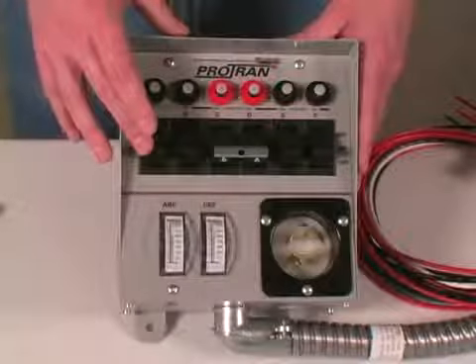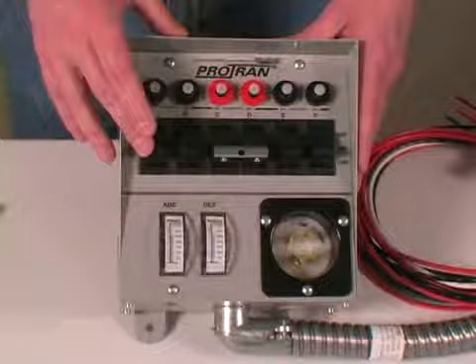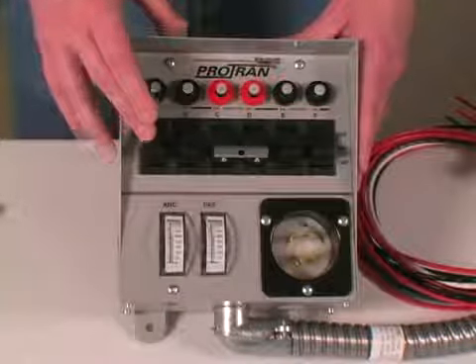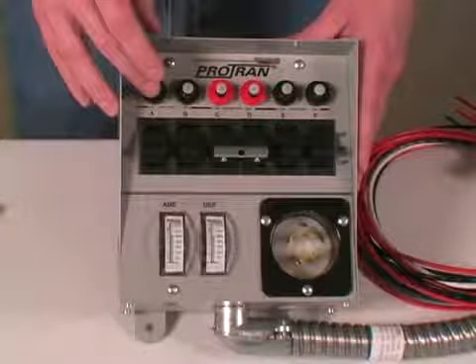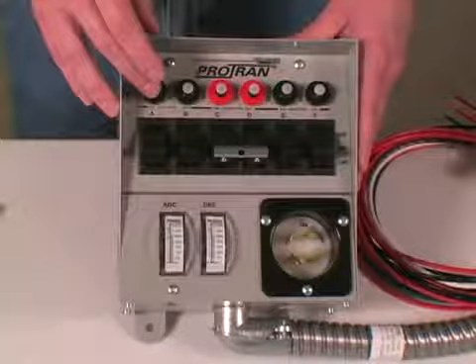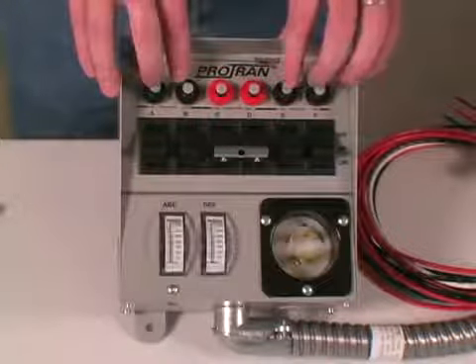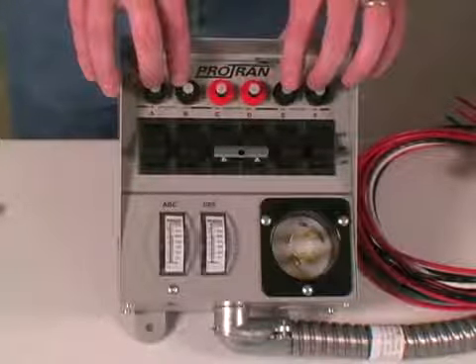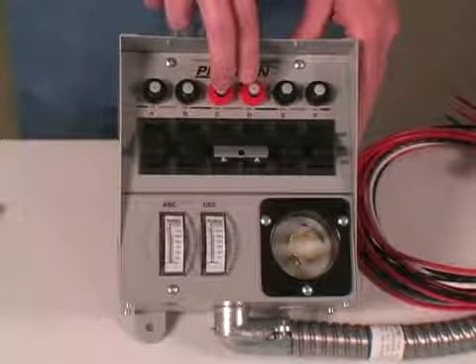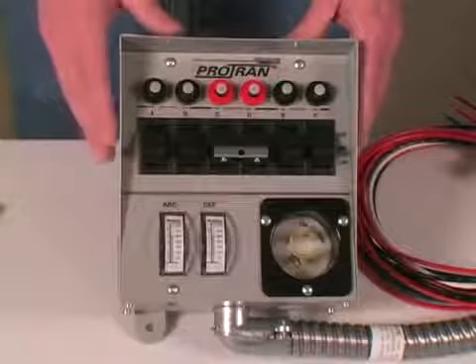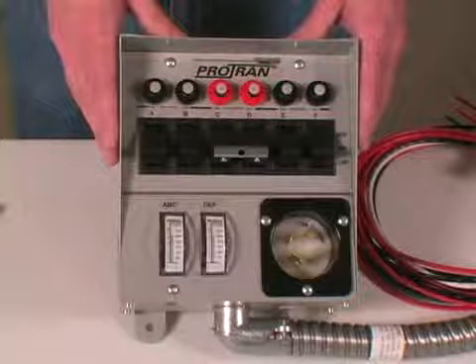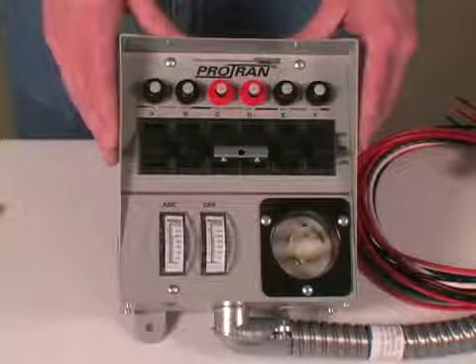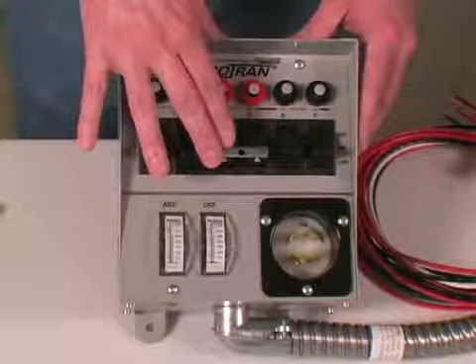These are the switches that transfer power from the utility to your generator, and these are the circuit breakers that correspond to each switch. The transfer switch circuits that have 15 amp breakers can be installed on any 15 or 20 amp household circuit, but the transfer switches that have 20 amp breakers can only be installed on a 20 amp household circuit. If you have a double pole or 240 volt circuit you would like to operate, like a well pump, it must be on the center or C and D circuits.